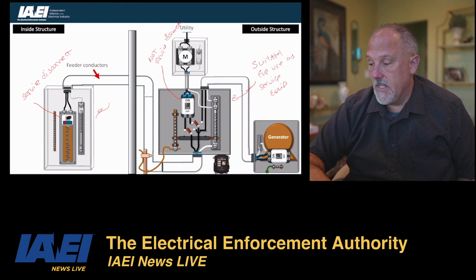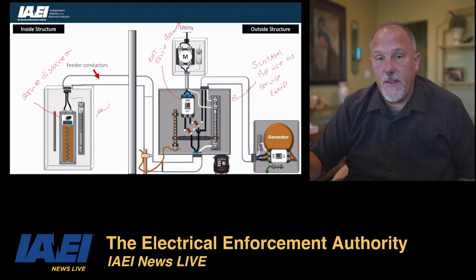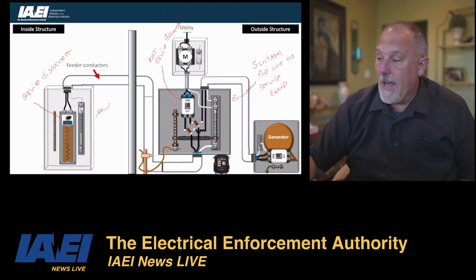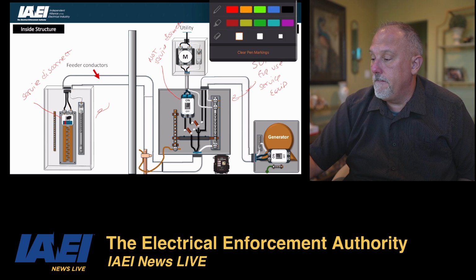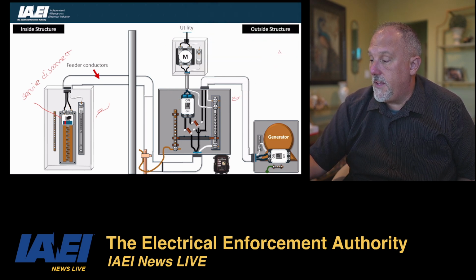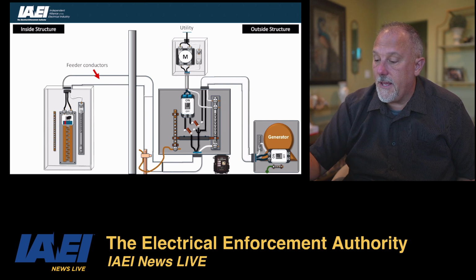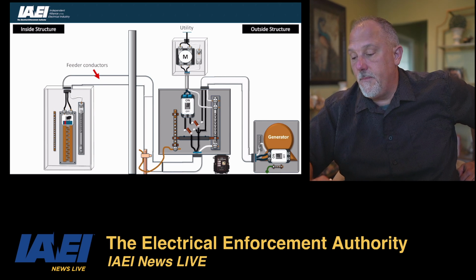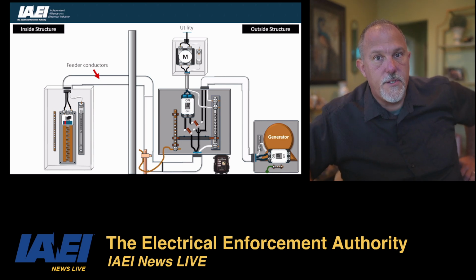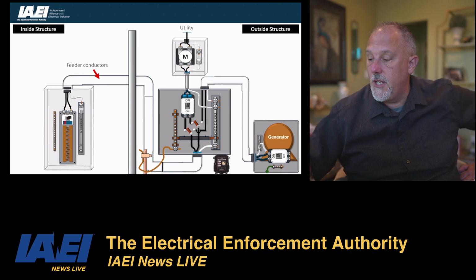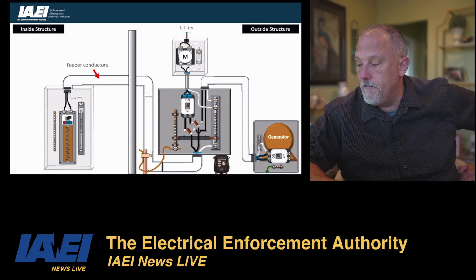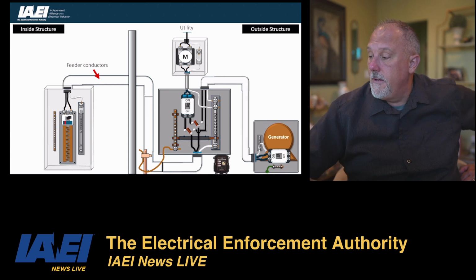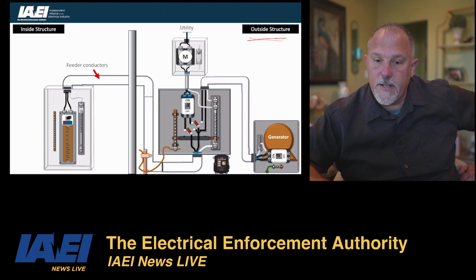equate to that. So in any case, if I'm doing this as a new construction, or if I'm adding to an existing, then this is basically how I would put that together. You would want to disconnect that, make sure that the panel board that's in the house is not suitable only for use as service equipment, and you have your transfer switch. That main breaker in that transfer switch is now your service disconnect. It can also be your emergency disconnect if that's on the outside of the structure. And I have all of that equipment that's on the right-hand side on the outside.